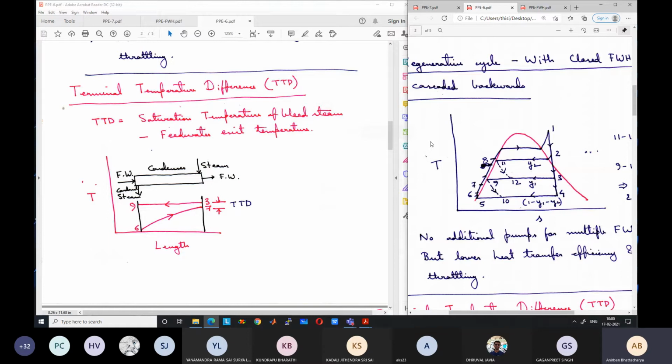So what is the implication of that? The terminal temperature difference in this case is negative. So it can go negative also. For the simple case, I said 3 to 5 degrees. But for this type of case, T8 is kept below the temperature T2, and it can go negative also. It is up to the designer to decide the actual value of T8, depending on the exact situation. For this case it is negative because T8 is marked above T11. So it can be negative also, and that is what I will show here, for the other case.